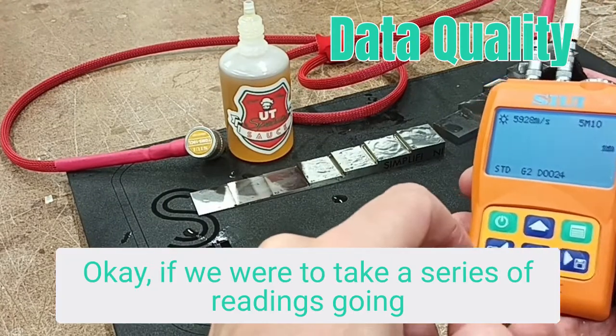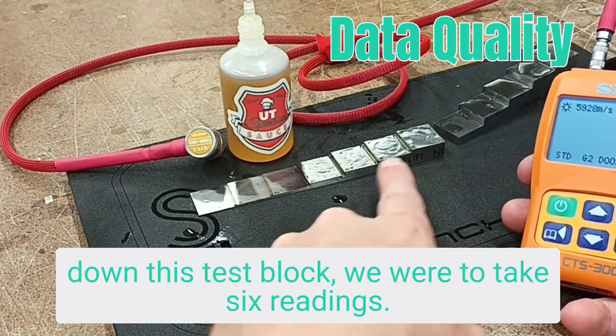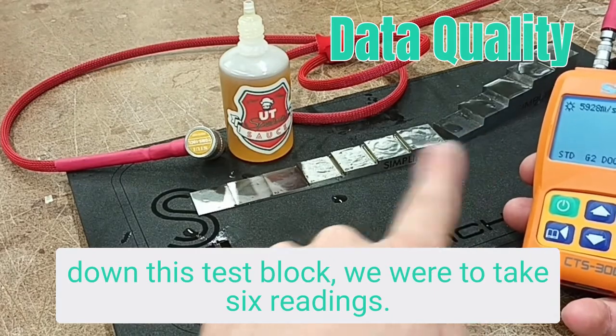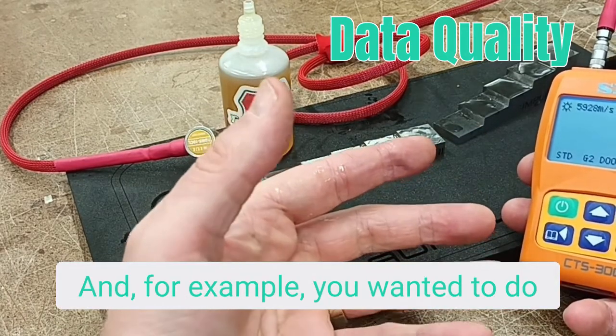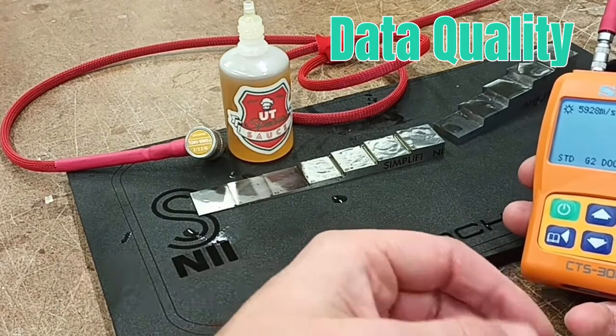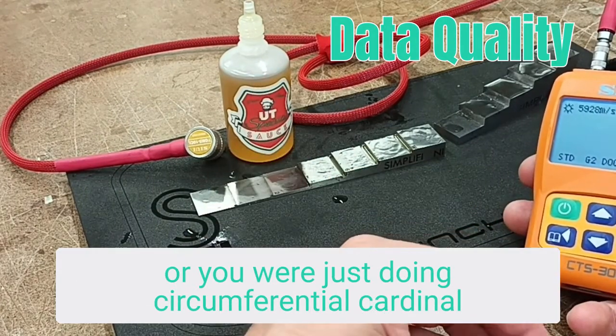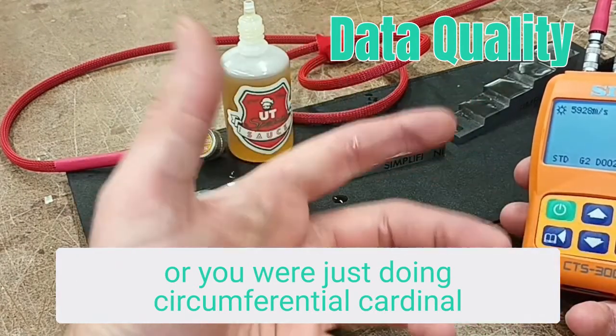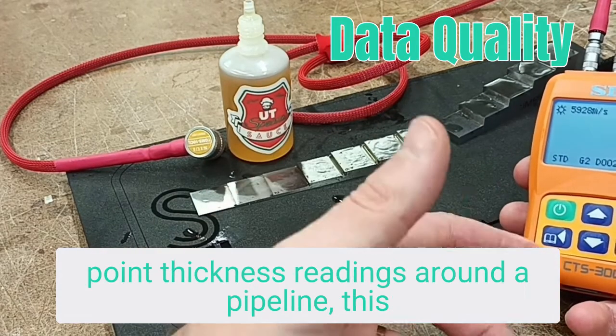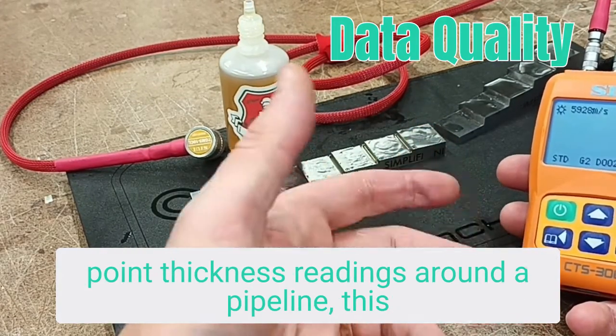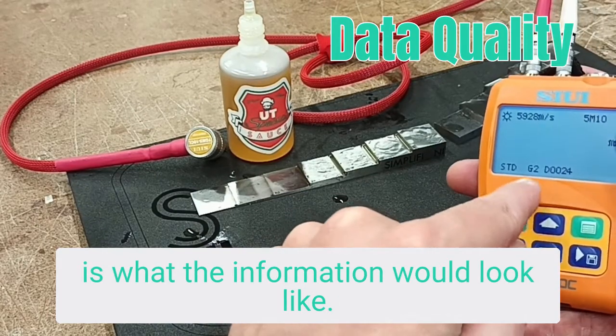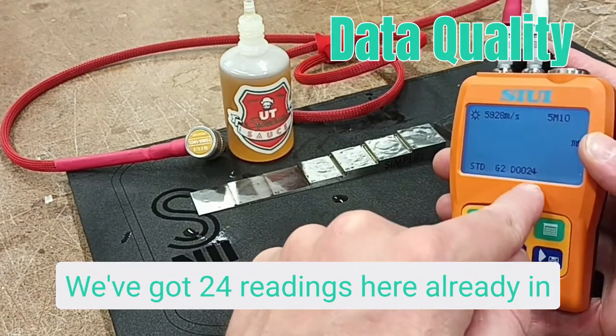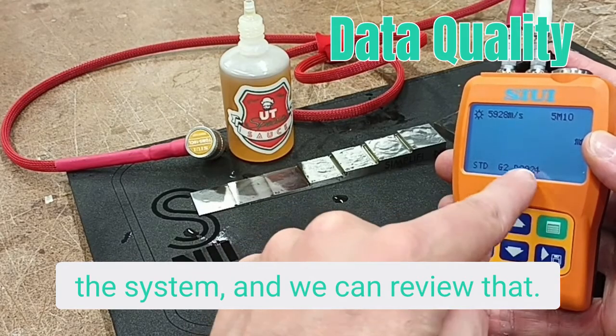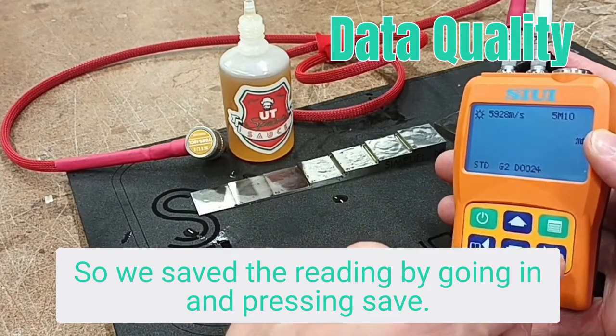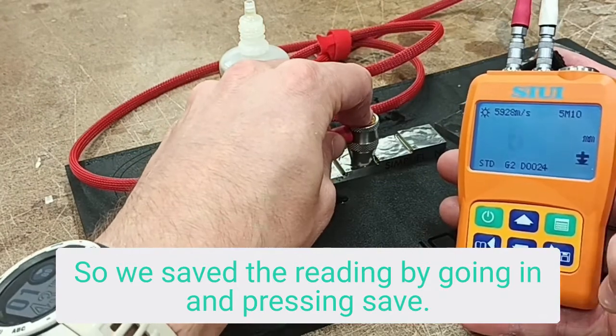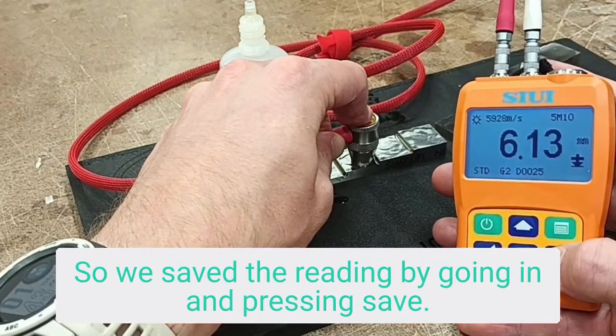Okay, if we were to take a series of readings going down this test block, we were to take 6 readings, and for example, you wanted to do that 4 times in a row, whether you were doing a grid map or you were just doing circumferential cardinal point thickness readings around a pipeline. This is what the information would look like. We've got 24 readings here already in the system, and we can review that. So we saved the reading by going in and pressing save.